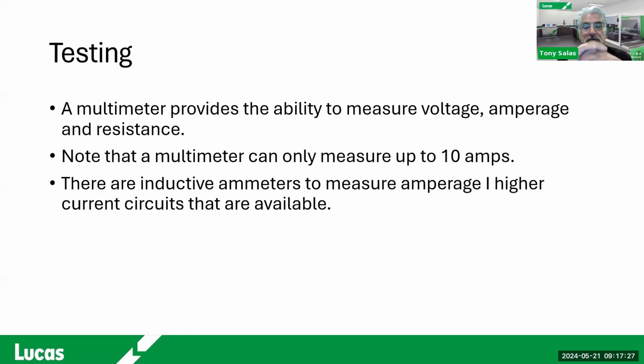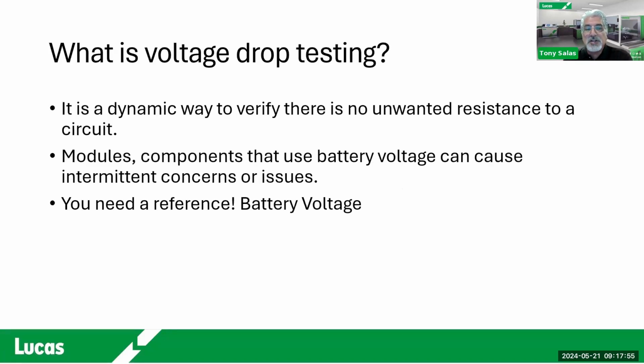So therefore it's fused. And it's funny, because every time we do an electrical class or I go to a shop, we find that the fuses are burnt on those meters. So you definitely want to check those meters. Every manufacturer of meter will have their way of telling you how to check it, but you do want to inspect to make sure that fuse is not burnt on your meter. But remember, the maximum that a meter can handle is 10 amps if you're doing amperage measurement. But we're not going to be doing amperage measurements in this presentation because we're talking about voltage drop testing.